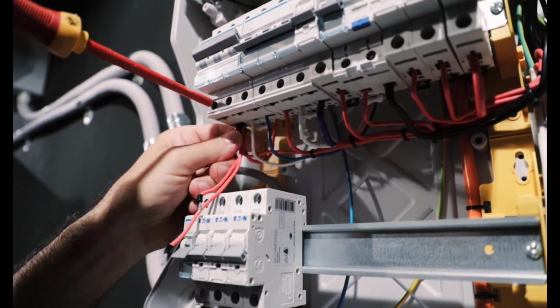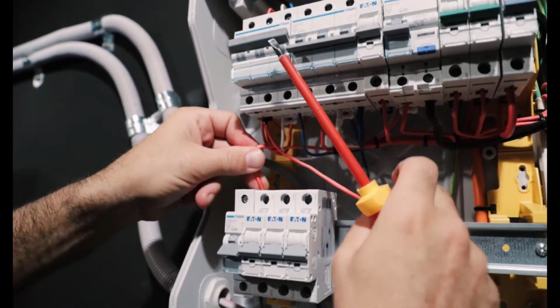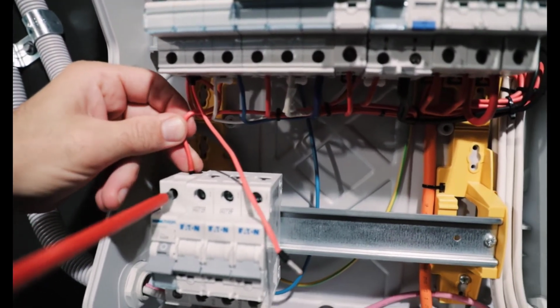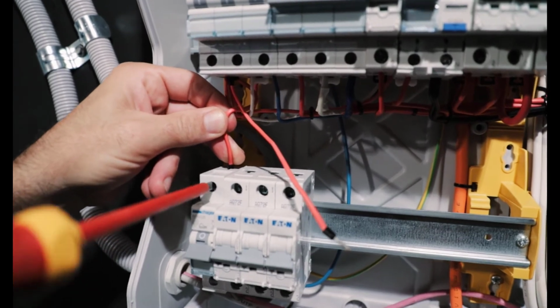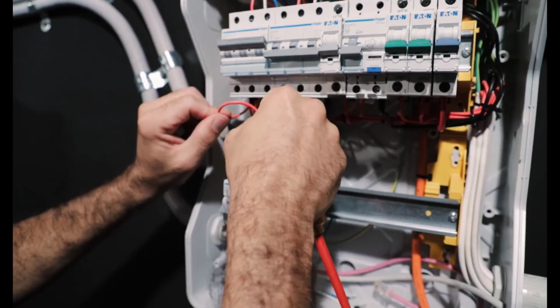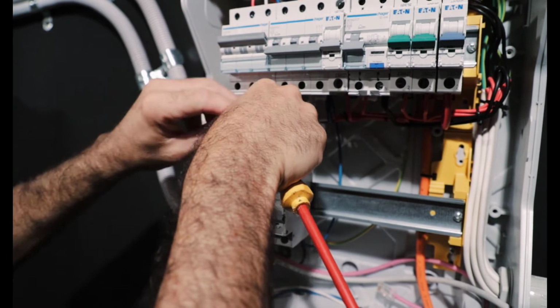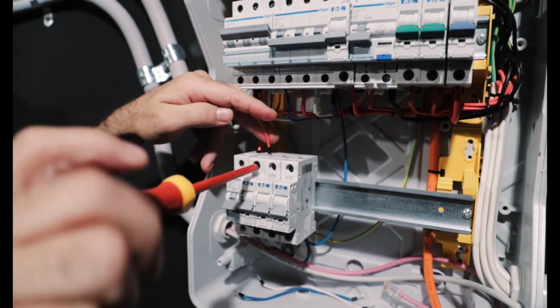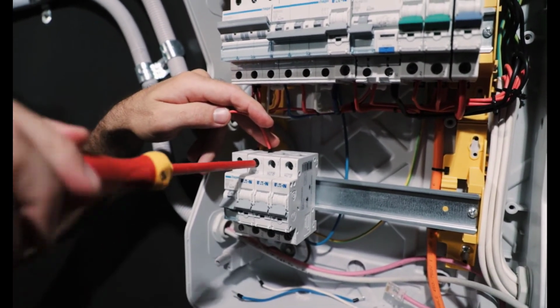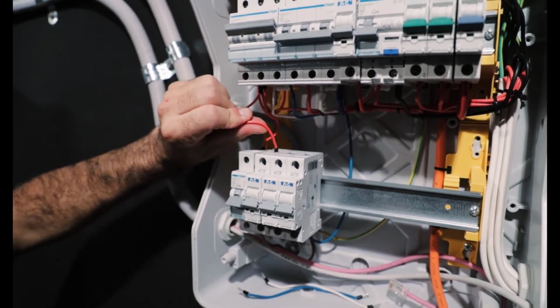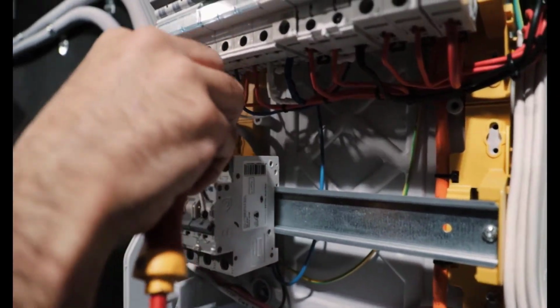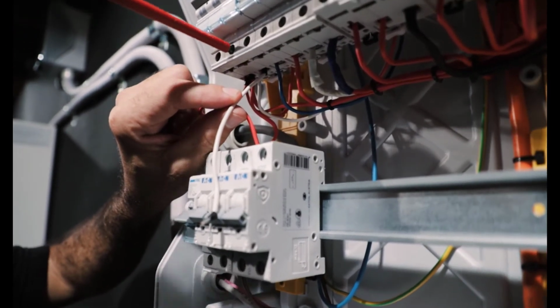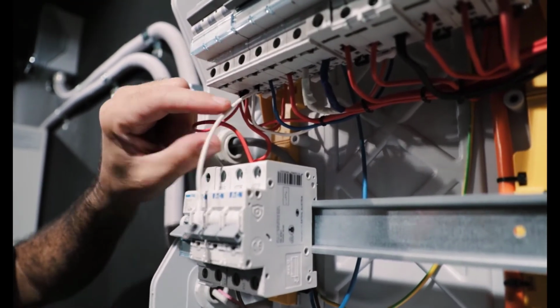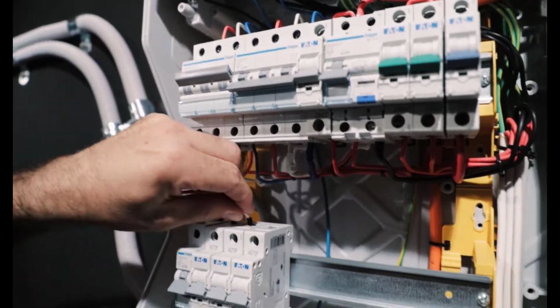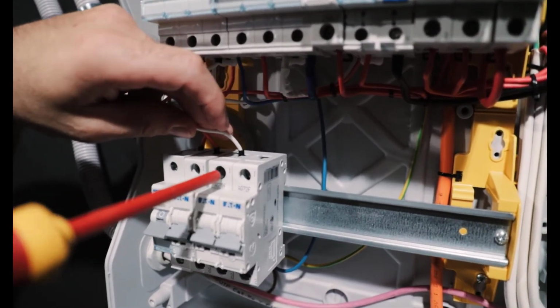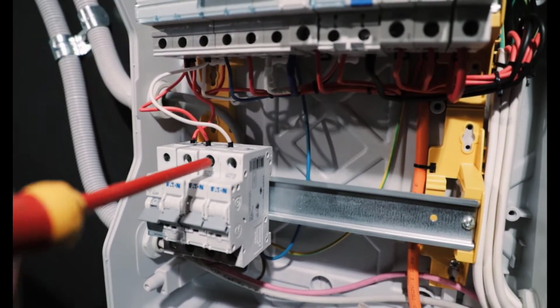Now this can be slightly confusing, or slightly challenging at times, because it's a little bit of an interpretation within the standards whether or not the isolator for the Sonnen meter needs to be a latched 3-phase isolator. We actually need to be able to isolate out the phases separately to test whether the meter has been set up correctly. So we need each of those MCBs to be unlatched so that we can switch off L1, L2, L3.